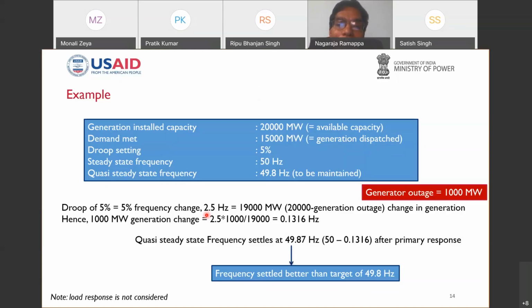Therefore, if you have a generation installed capacity of 20,000 megawatt and demand met is about 15,000 megawatt, that is the generation dispatched, and droop setting is 5%, steady state frequency is 50 Hertz, quasi steady state frequency is 49.8 Hertz, and assume that 1,000 megawatt of loss of generation occurs. Droop is 5%. Initially, we have 20,000 megawatt of generation available, but with the loss of 1,000 megawatt, we now have 19,000 megawatt. Therefore, 5% change in frequency on 50 Hertz is 2.5 Hertz. If all the machines are in governor control, primary control, 2.5 Hertz change over 19,000 megawatt, for the 1,000 it comes to 0.1316 Hertz.